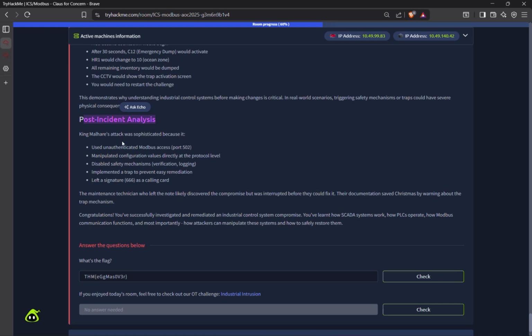That's what was sophisticated about the attack - firstly unauthenticated Modbus access, where the attacker entered through port 502, and they manipulated the configuration values directly at the protocol level, and they disabled the safety mechanisms. We did this, and every time whatever goes in has to be logged. Audit can be used for several purposes after post incident analysis.